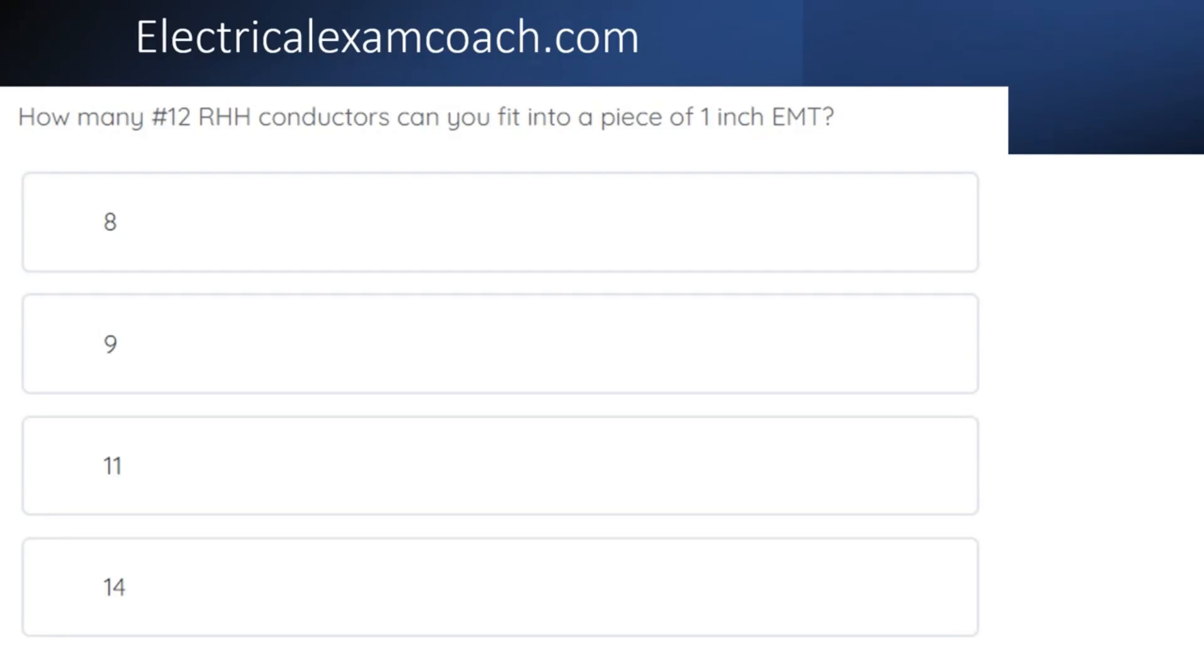How many number 12 RHH conductors can you fit inside of a piece of 1-inch EMT? The correct answer is 9.